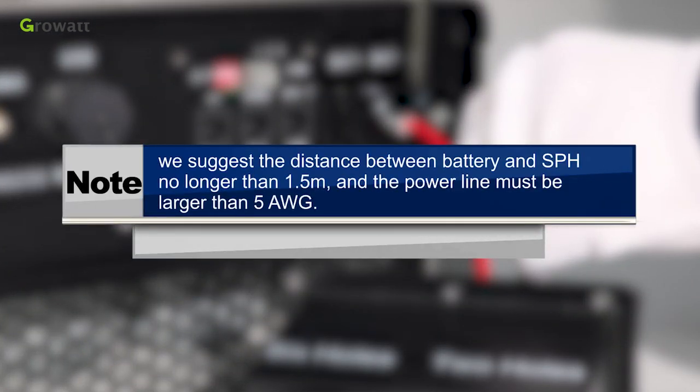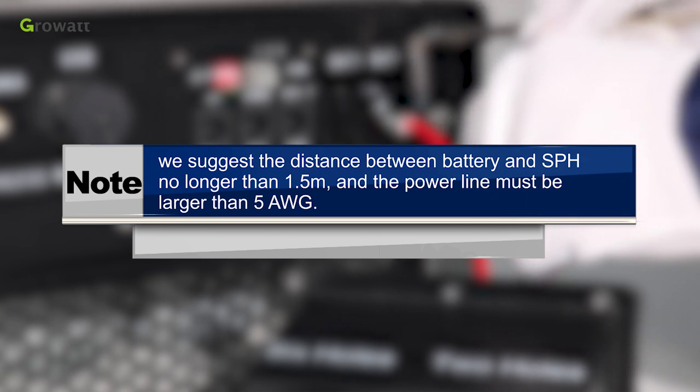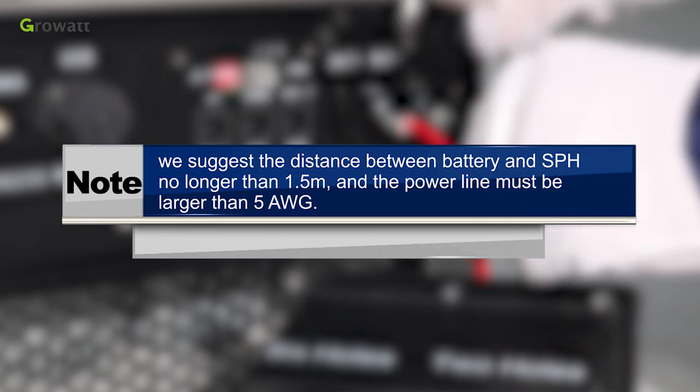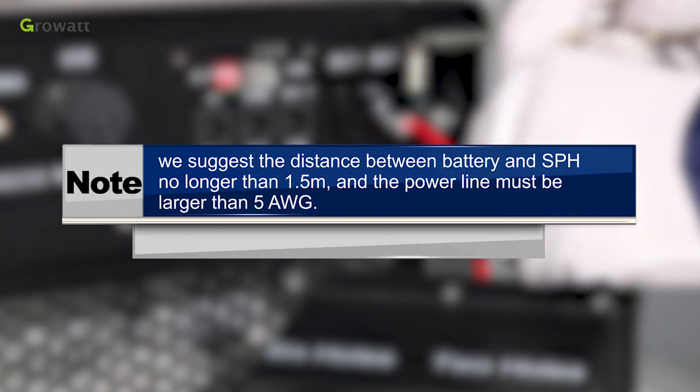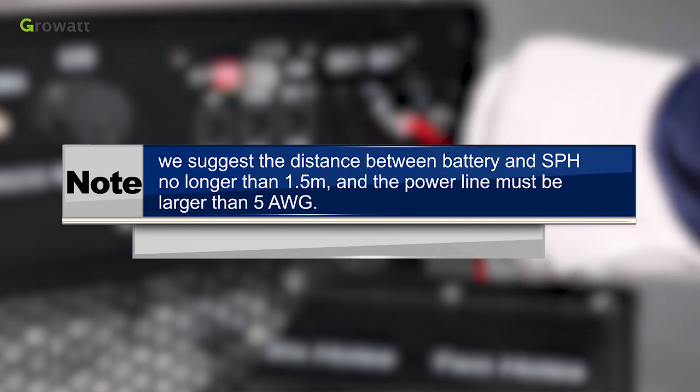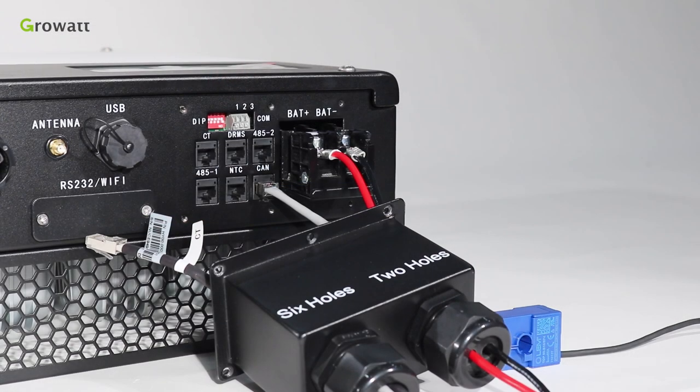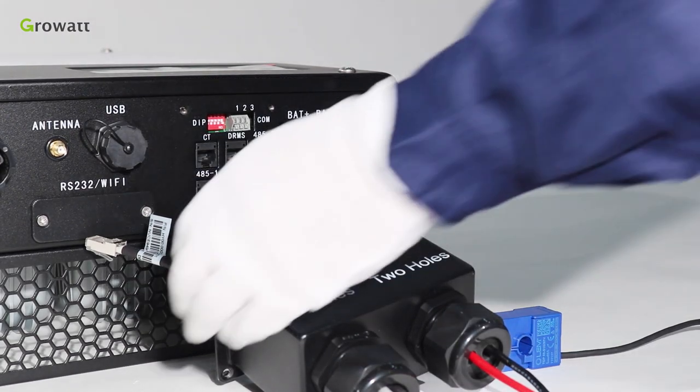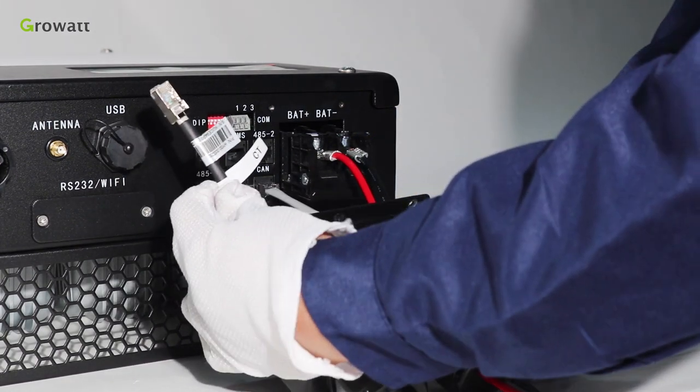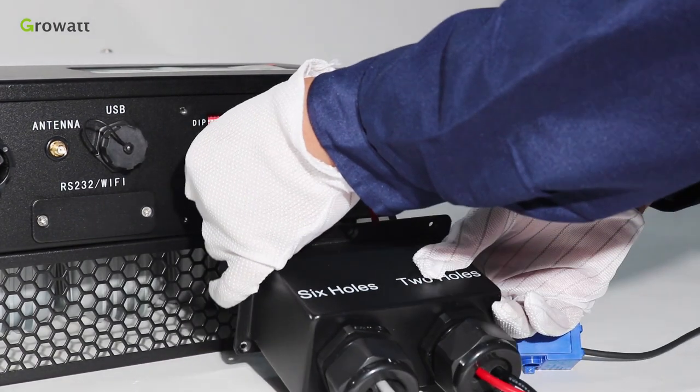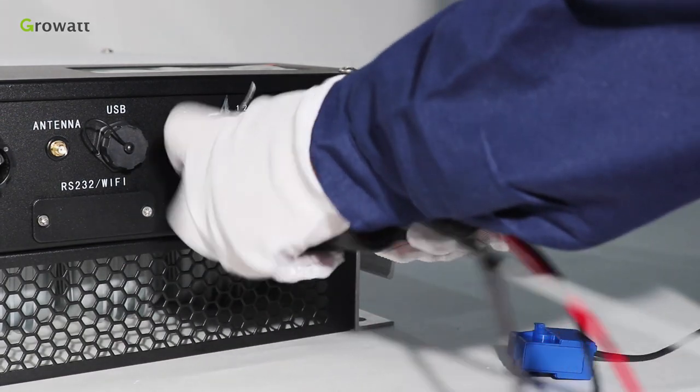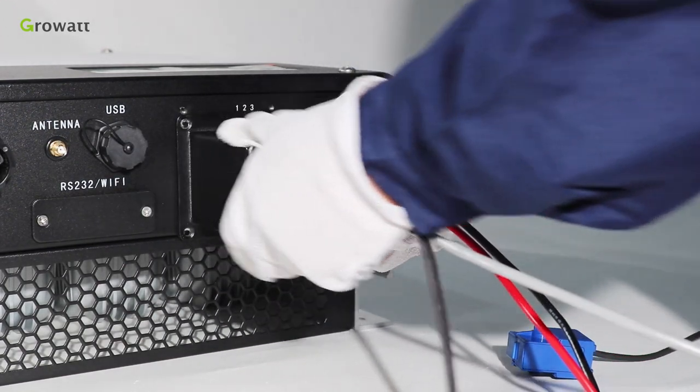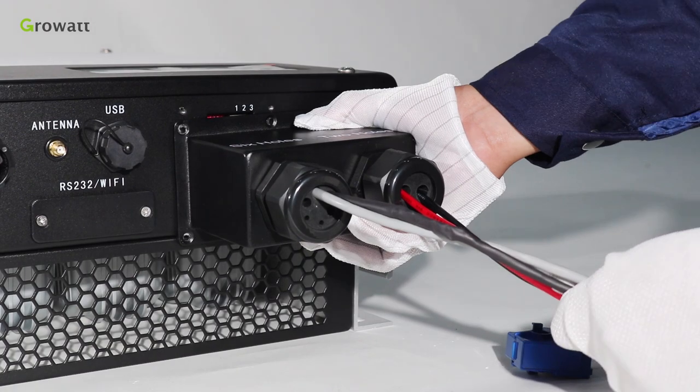Note, we suggest the distance between battery and SPH no longer than 1.5 meters, and the power line must be larger than 5AWG. For communication connection, thread the CT and battery communication cables into the waterproof cover as well. Connect them into the corresponding terminal and connect the waterproof cover into the inverter finally.